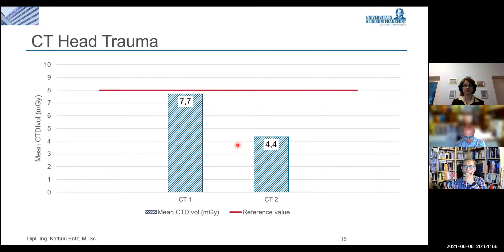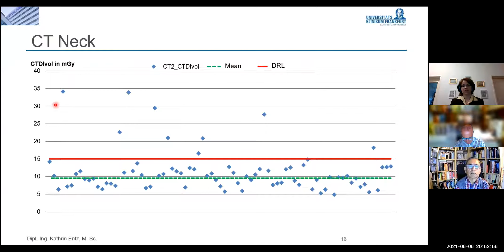A different problem we had at our radiology department was with a scan of the neck, again computed tomography. You can see here different dose values over a certain time period. The red line indicates the dose reference level, which is a CTDI of 15 milligrays for the neck. The green dashed line indicates the mean values for our neck scan. Generally we are at roughly 2/3 of the dose reference level, so we're even better than before, I would say. But you can also see up here some values really exceeding the dose reference level. For example, these values are more than 3 times above our mean and more than twice the dose reference level.